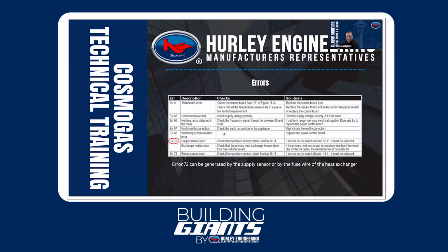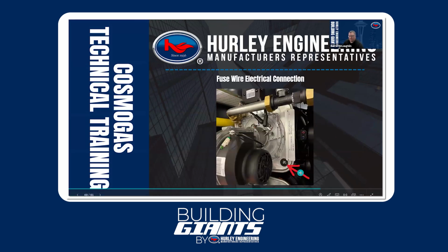It'll do it automatically. By the same token, we've got this error 72, and if you remember, that's the fuse in the front of the boiler. Let's say you had a runaway boiler or it's been scaled up severely and it's not able to remove the heat from the heat exchanger on the water side. If you get hot enough to pop that fuse, then you'll get this error 72. So just keep that in mind. If you can't reset that, then that's likely because that fuse has been blown. And here, that's the location of the fuse on the front of the boiler, just for reference, in the bottom right corner there.